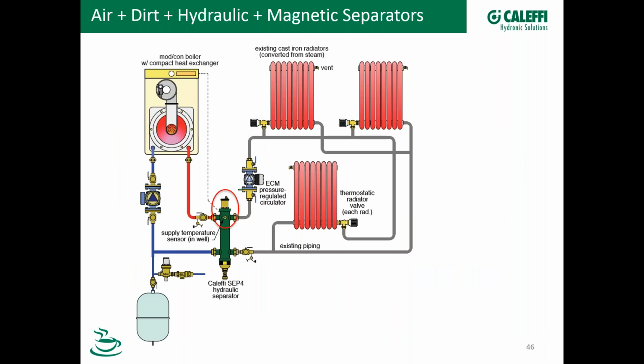So we're going to go from air plus dirt now to what we call our SEP4. This is air plus dirt plus hydraulic, and it has magnetic separation. This device is a 4-in-1, and what it's doing is separating the primary circuit here with our ModCon boiler from the secondary circuit serving our zones. Now what we have here is this upper section. Again, there is our air separator. The coalescing media right inside here is scrubbing out the air, and the air vent is releasing it to atmosphere.